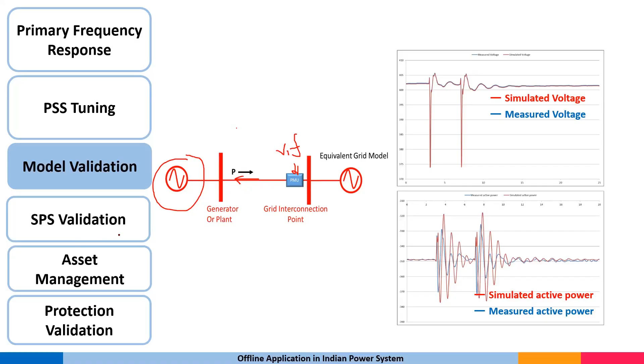Let us say for any event, we have the voltage and frequency for this node. Okay. So what we do is we feed this information to the generator model, and it replicates this voltage and frequency and tries to change its P and Q accordingly. And we compare the actual P and Q with the simulated P and Q that we obtained from the actual V and F. We see whether it is responding well or not, or whether there is a requirement of tuning the generator parameters, or checking the parameters of the generator. So you need a very good, accurate model so that you can understand the dynamics of the system. For that also, synchrophasor is helping a lot.